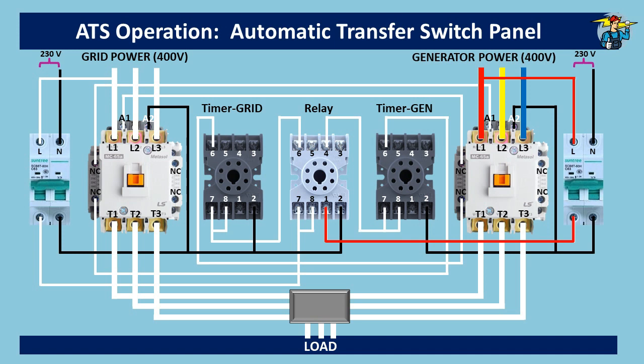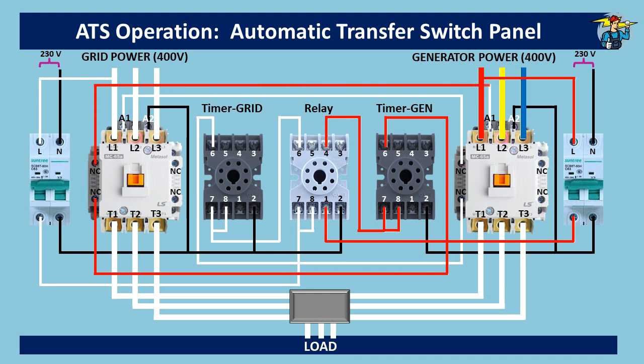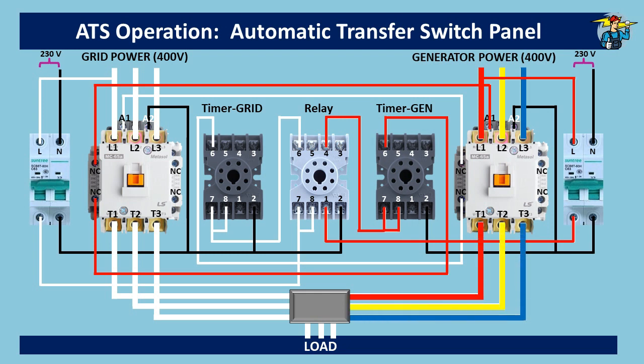Relay output port 4 is at normally closed position and allows power from port 1 of the relay to flow to ports 7 and 8 of the generator timer. Although the relay is powerless, the generator timer is powered. After the set delay time, port 6 also gets power, allowing connection to A1 of the generator contactor. This connection also goes through the normally closed auxiliary contact of the grid power contactor to make sure it is at OFF position. The generator contactor turns ON and the load gets three-phase power through the generator.